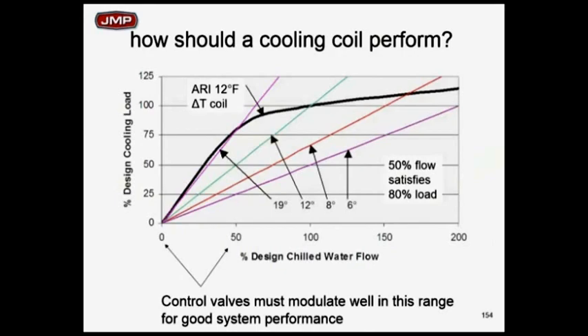That's what you design. That's what your chiller plant was picked on. That's the delta T required. That's how you keep the return chill water temperatures up. That's how all these good things are going to happen to you if I can hold at 12 degrees. Now, ARI goes a step further. We don't normally run cooling coils at 100% load. I would say 50% load would be where we normally are. So with 50% load, let's assume we'd have 50% chill water flow. Let's just take a look at half flow.